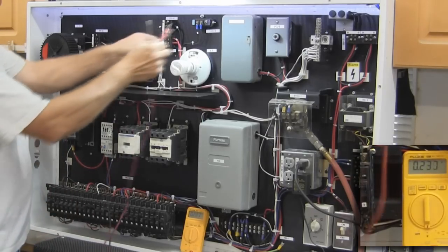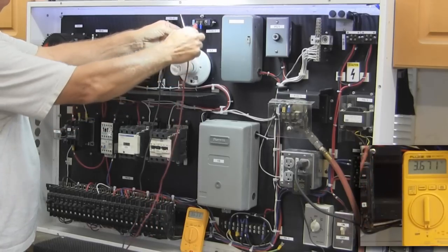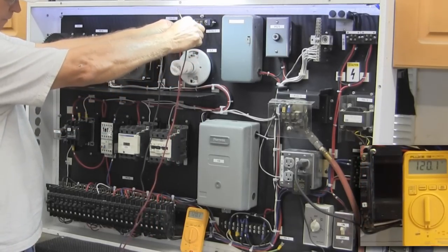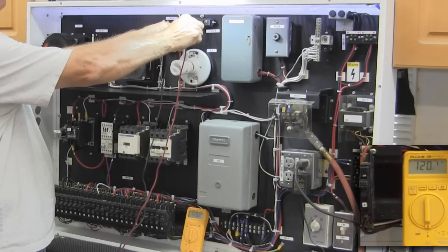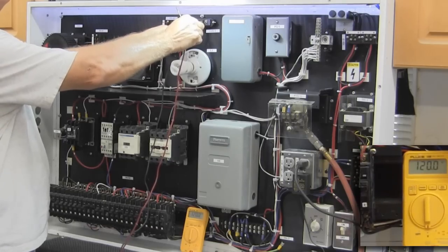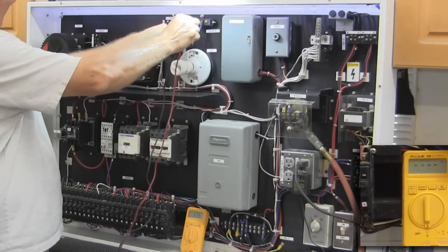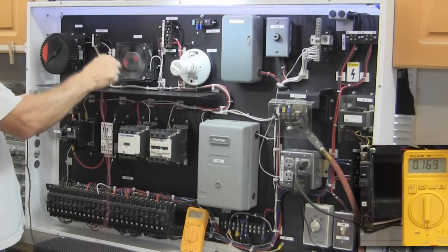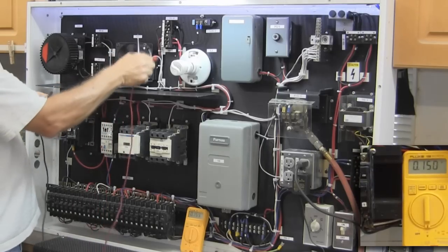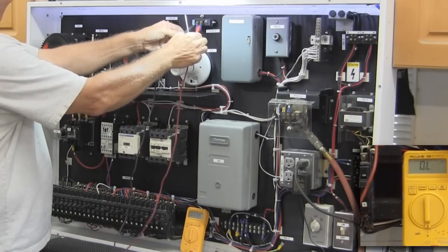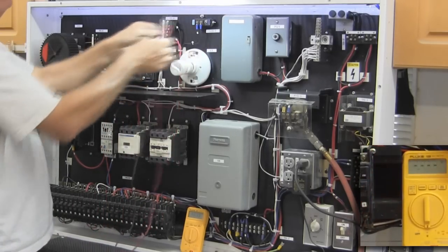Let's cut the power out and if I go between these two I'm getting 120 volts. And the reason for that is I'm getting the power coming in here but I'm reading through the neutral on this fan motor. So if I were to disconnect that neutral and test between these two I wouldn't get anything.